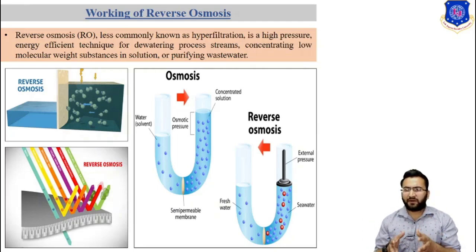The pressure required depends on the concentration of the salt solution on the rejection side of the membrane. Running a system at 1100 ppm on the concentrate side requires application of over 200 psi pressure. A seawater system at 33,000 ppm generally runs at 800 psi. A household reverse osmosis system usually runs at 50 to 70 psi.